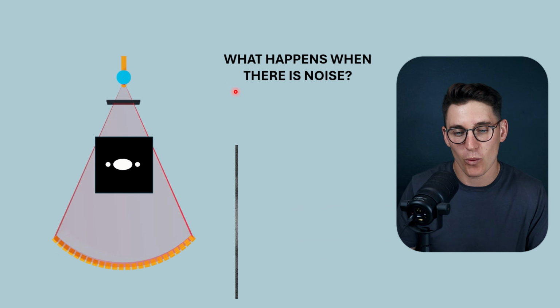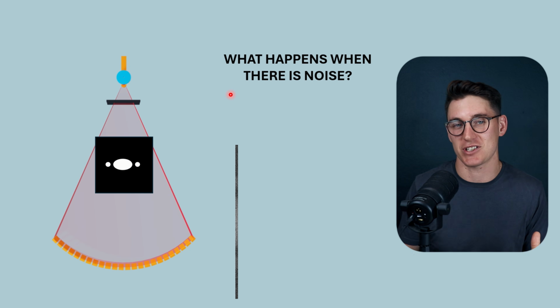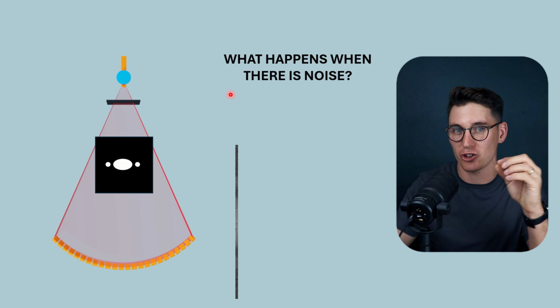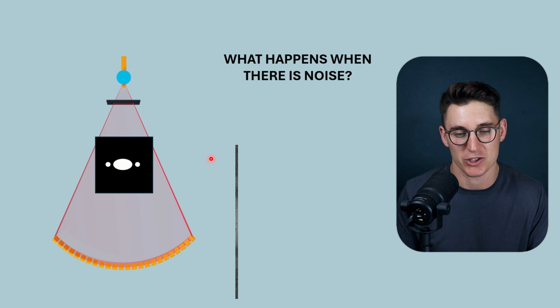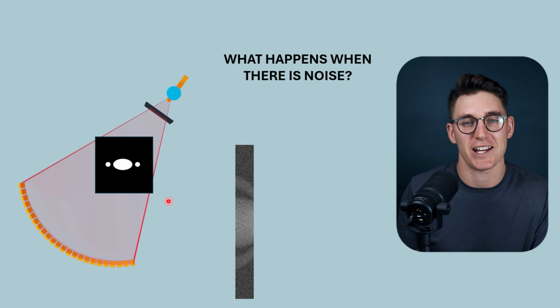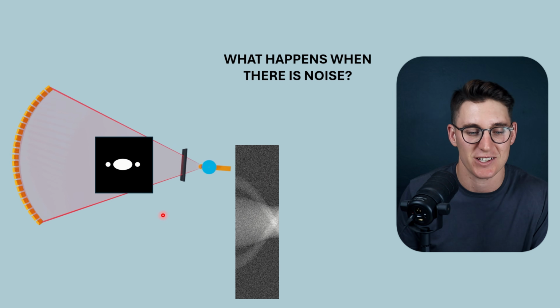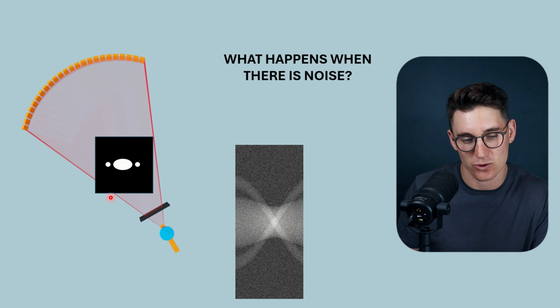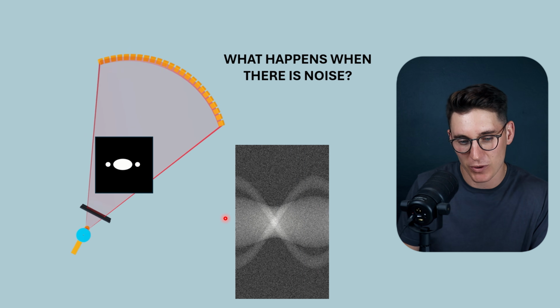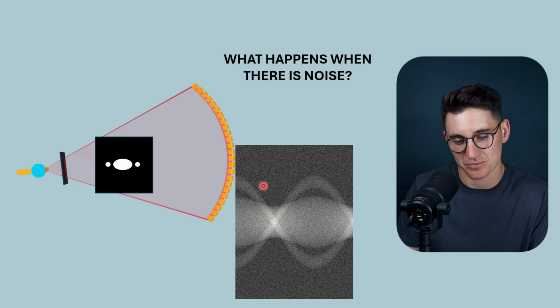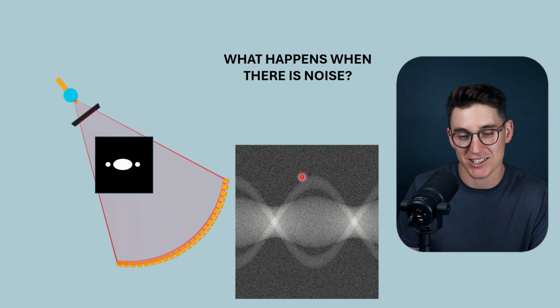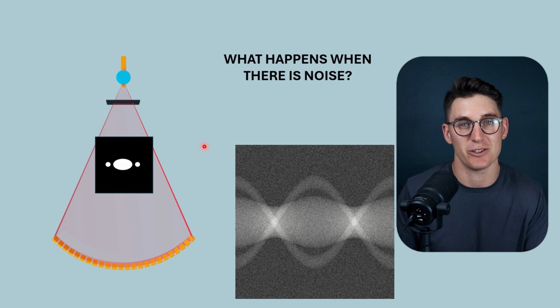Well, the main issue comes when we're looking at noise. We know inherently there's going to be noise in our image, and later on when we look at image quality, I'm going to show you how noise is introduced into the image. But say we were to create a sinogram here, but we were to add noise into the sinogram, either through the detectors or through patient factors here. We can see that there's background noise. How then does filtered back projection deal with this background noise? Well, it doesn't deal with it very well.